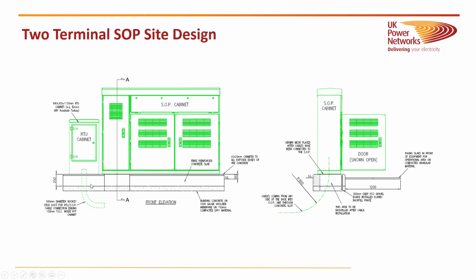An important point to note here is that, as Luca said, there are 2 link boxes that need to be installed in front of this. That allows you to bypass it if you want to just operate the network in a radial system. But when you do want to use the SOP, you need to be able to connect each feeder separately to the SOP, so that it can share power between the 2 without transferring any fault level. And lastly, this has been designed to make sure there are no electrical connections or anything exposed, so that the public are safe.